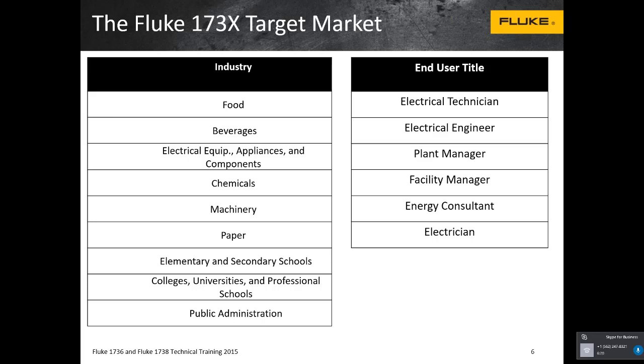So essentially, why would you be doing a load study? Usually the reason would be to see how much flexibility there is in the existing service to add additional loads. Sometimes rather than spending the money to change out a panel, change out transformers, or increase the service size, you would do a load study to verify if that's really even necessary or warranted.